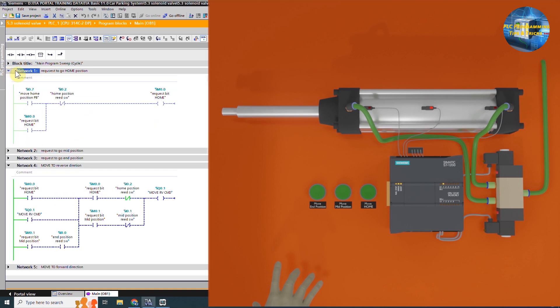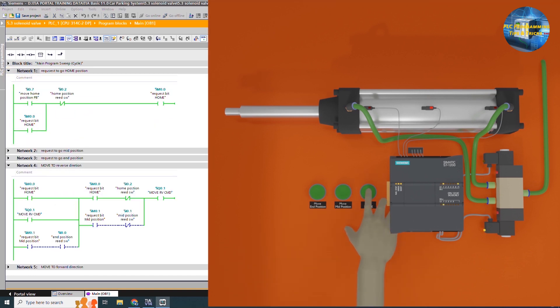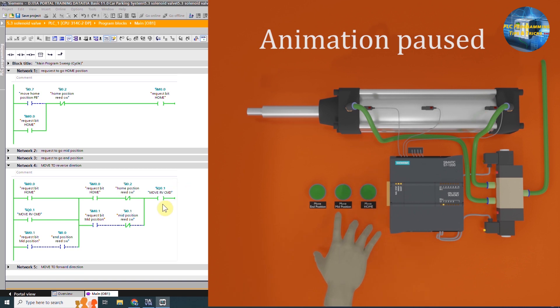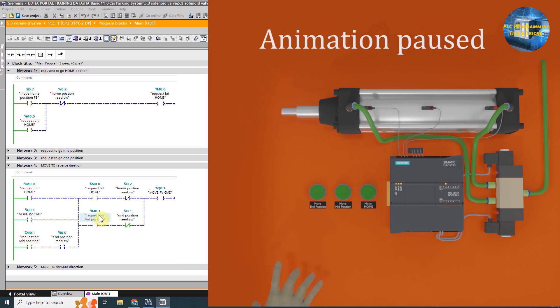Next, if we press the home push button i0.7, the bit m0.0 for the home request turns on. This bit in network 4 turns on the Q0.1 reverse command. As soon as the cylinder reaches the home position, the i0.2 reed switch turns on and this normally closed contact opens and turns off the Q0.1 reverse command and the cylinder stops at the home position.